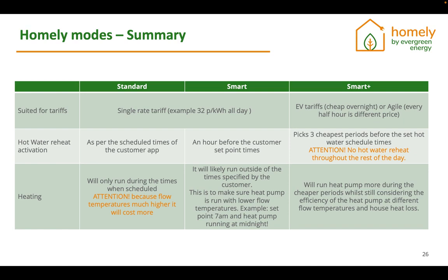And in terms of the heating, it will likely be running outside of the times that have been specified by the customer. This is to make sure that the heat pump is delivering that heat into the house at the lowest flow temperatures possible. So even if there is a set point, let's say at 7 a.m. in the morning, and you're currently at 20 degrees and it's midnight, the heat pump might already be running, trying to make sure that it doesn't lose too much heat overnight so that it doesn't need to run the heat pump really hard when it needs to actually get to your set point later on.